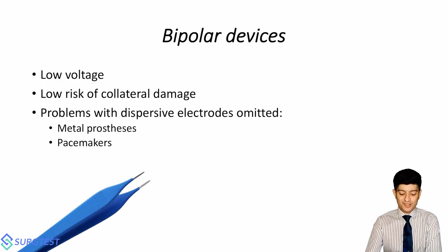It is perfect for use in neurosurgery because they are working in a surgical field that is sensitive to electro energy. In wet surgical fields, again, very, very useful. If you apply monopolar energy to a wet field with a lot of fluid within the cavity, the fluid ends up conducting energy across, the current density is lower and you don't end up getting the desired thermal effect. In contrast, you can put in a bipolar device in a completely wet field, but eventually the amount of tissue or fluid contained within the jaws is the only part of that surgical field which is going to be involved within that circuit. So energy delivery is still going to be as close to what you desire as possible.